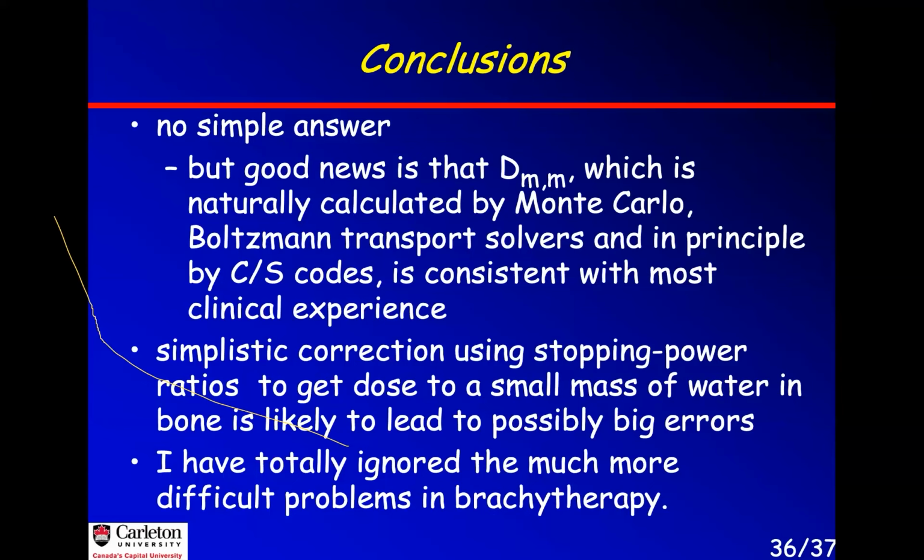Sorry, can I ask a question? I want to ask you one question. By calibration factors, we convert the charge to the dose in water or dose in medium. And I want to ask you, for Monte Carlo calculation, there is a CT-to-electron-density curve.